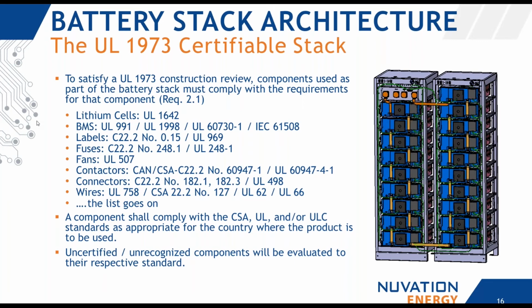And it's that last point that's the real sticking point when it comes to a 1973 battery stack. Imagine, as a project manager responsible for certification budgets and schedules of a battery stack, discovering that the engineering team selected components that now must go through additional testing or be substituted out for certified or recognized components. It's rare to find a drop-in certified or recognized component, and sometimes that component simply doesn't exist. So when setting out on the road to a UL 1973 certification, it's very important that the design team at its lowest level is aware of this high-level requirement, so correct components can be used from day one.